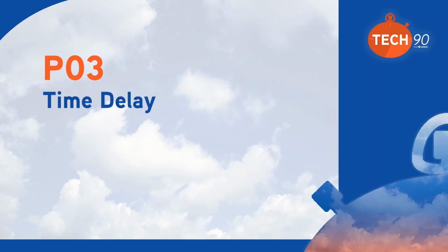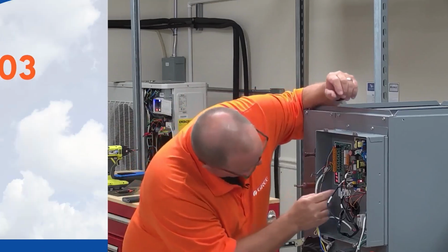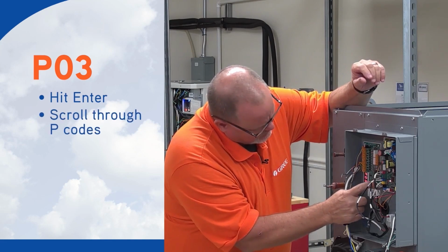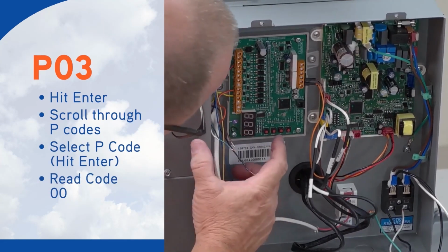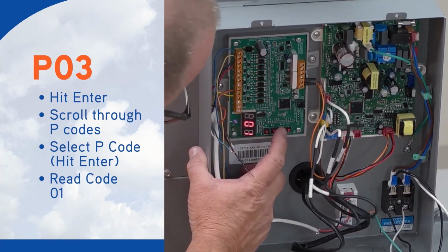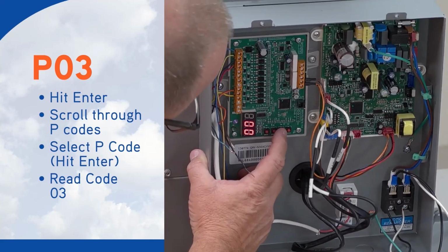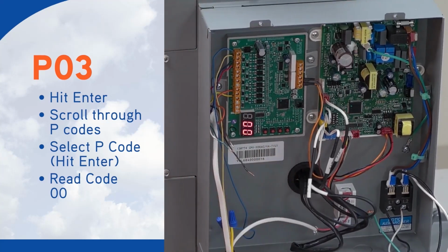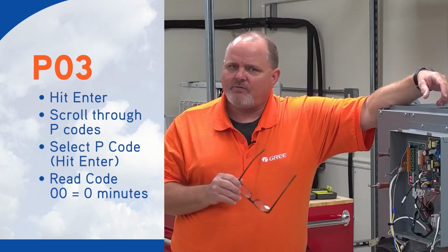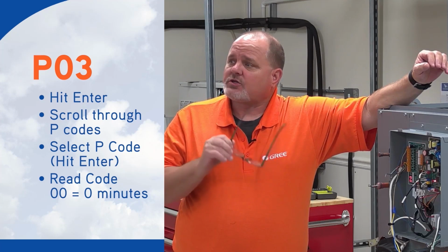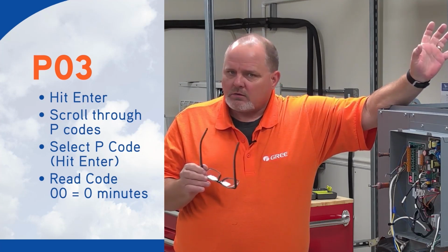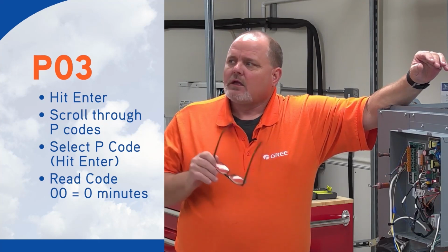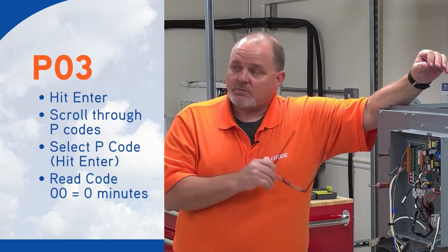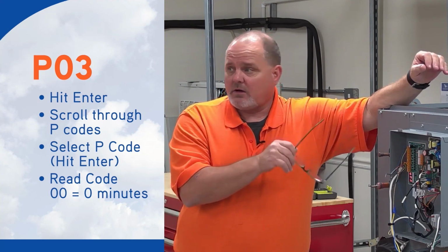The only other thing that we really got to worry about setting here is the P03, which is your time delay. Go in and hit enter again. P03, I hit enter. So you got 00, and then you just use the up down keys. You got 01, 02, 03, and 00. 00 is going to be 0 minutes, meaning heat pump operation shutdown, not blower. Remember, you're not controlling your blower, okay? So be very careful with that because it depends on the time delay for your blower too. Remember, G's not coming here.